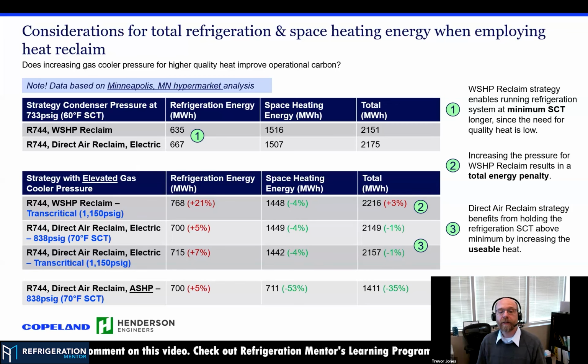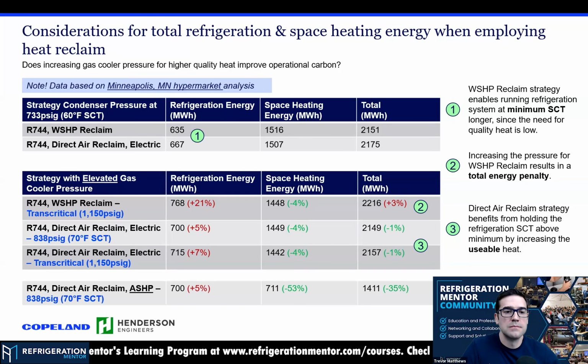But interestingly enough, going into the transcritical, and some of this actually had to do with the system architecture we were looking at, what we saw was going up a little bit was better than going all the way up to transcritical. Now, that was just for the systems we were looking at. On other systems, you'd want to go to transcritical, that'll be your best energy point. But it might not always be, so that's going to need to be looked into. Where do we want to run things?